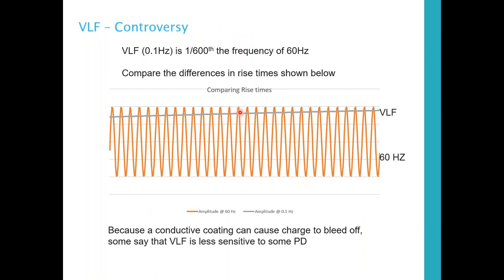There is a little controversy around VLF, just like there's a little controversy around almost all testing. In short, the controversy is that you're not doing a test under normal conditions. You're doing a test at a much lower frequency. Where the controversy comes up is you can get some bleed off from conductive coatings on whatever it is you're testing. Because of this bleed off, this current coming through the conductive coatings, some people don't consider it as effective, and say it's less sensitive to some forms of PD. Fair amount of controversy over it.